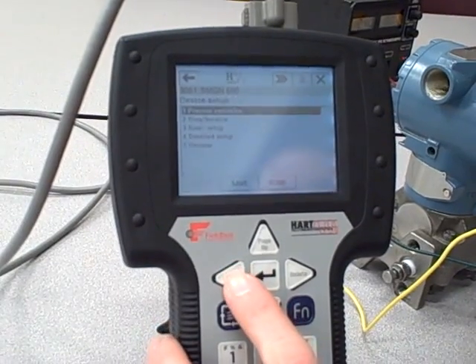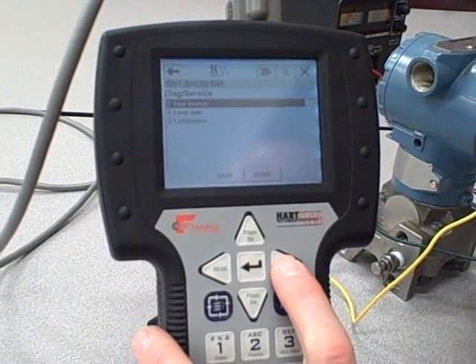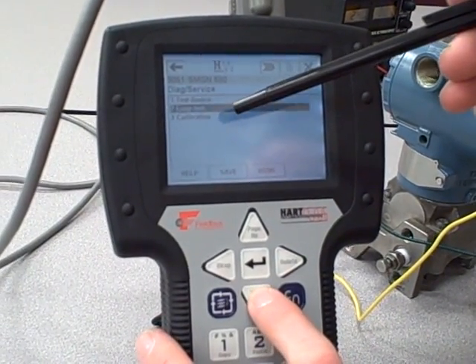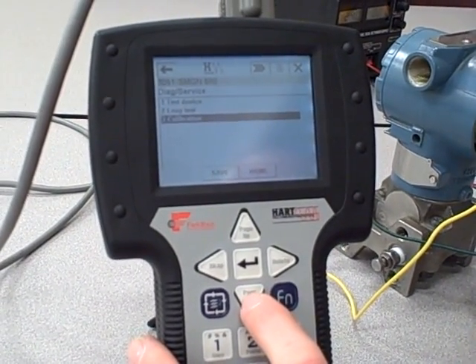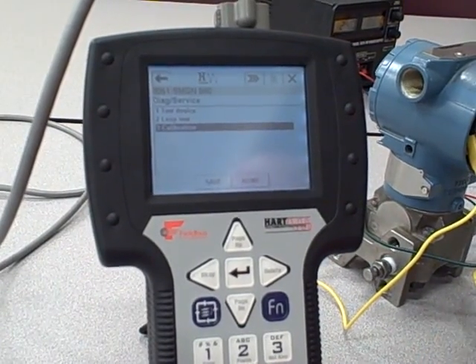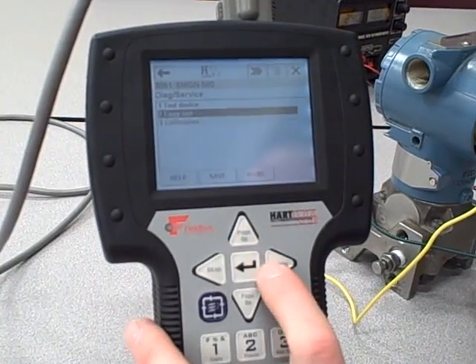I can go back, go into my next menu, Diagnostic Service. Here I can perform various self-tests. I can test the loop, and I can also go into calibration and do trim adjustments for both the sensor and the D to A converter for the 4 to 20 milliamp output. The loop test is something that bears some exploration, so I'll step into that.